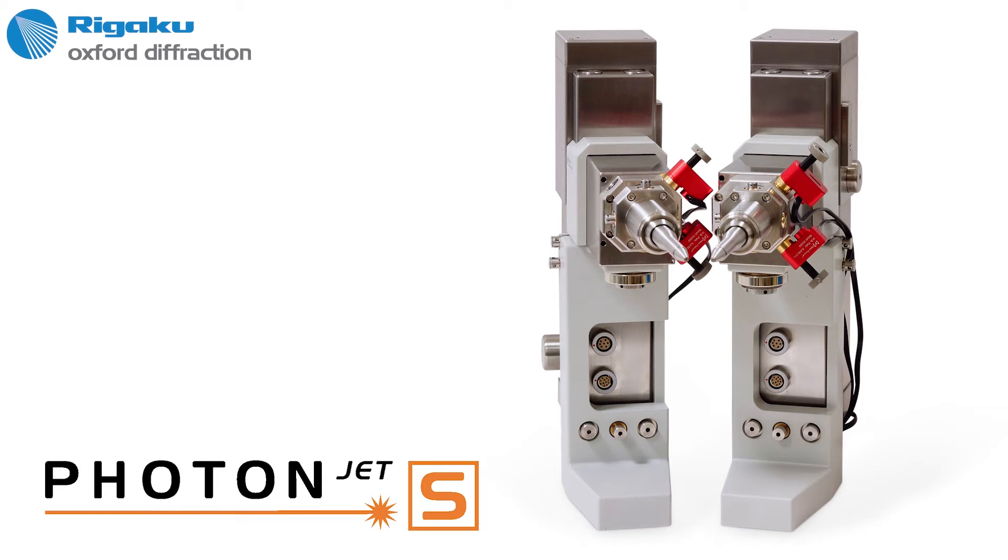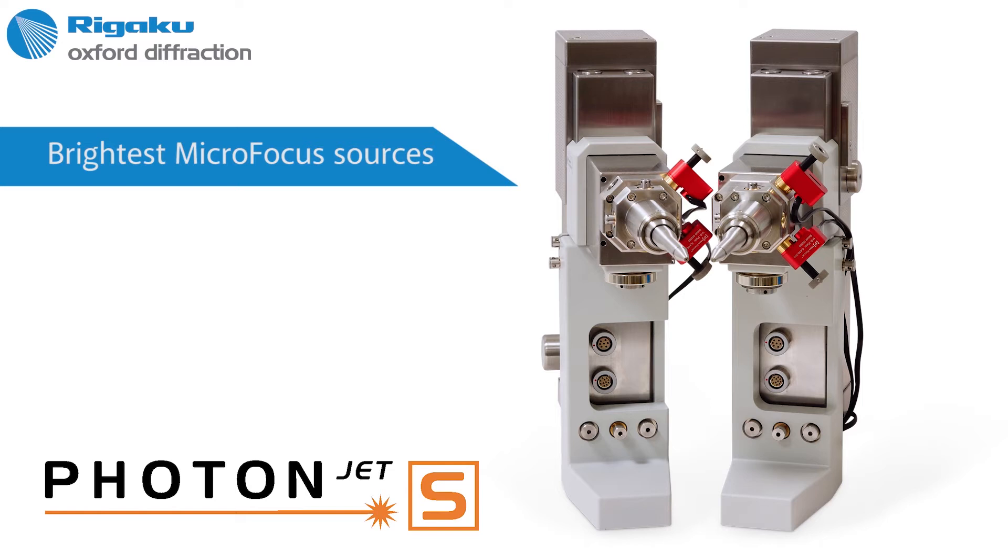The Photon Jet has been developed with two factors in mind. Firstly, to deliver increased photons at the sample, thereby achieving good diffraction from small and weakly diffracting samples. And secondly, to have longevity, reducing both downtime and maintenance costs.